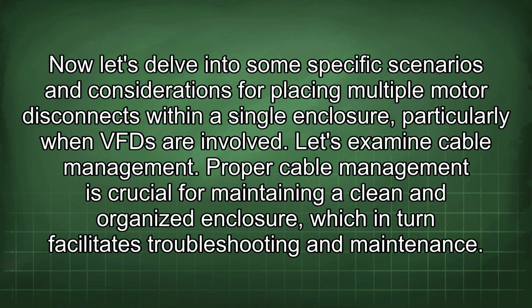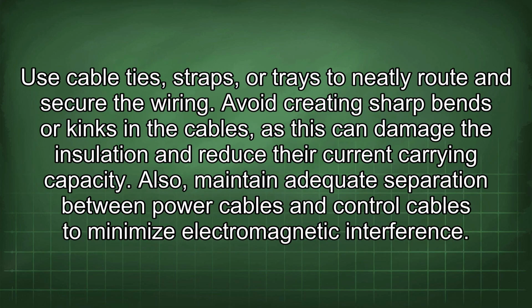Now let's delve into some specific scenarios and considerations for placing multiple motor disconnects within a single enclosure, particularly when VFDs are involved. Let's examine cable management. Proper cable management is crucial for maintaining a clean and organized enclosure, which in turn facilitates troubleshooting and maintenance. Use cable ties, straps, or trays to neatly route and secure the wiring. Avoid creating sharp bends or kinks in the cables, as this can damage the insulation and reduce the current carrying capacity. Also, maintain adequate separation between power cables and control cables to minimize electromagnetic interference.